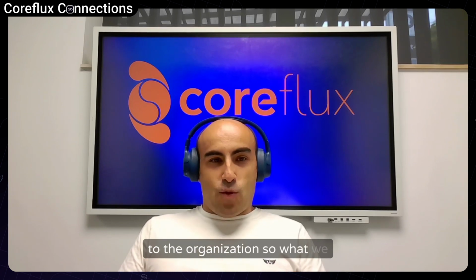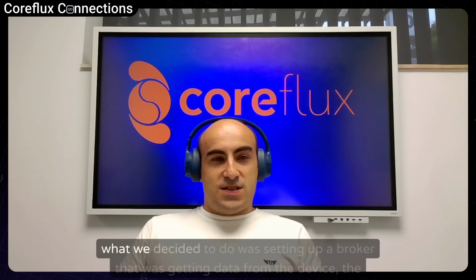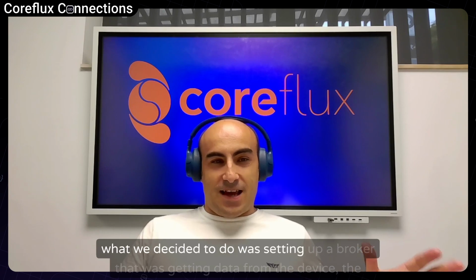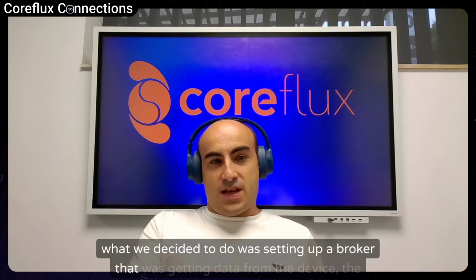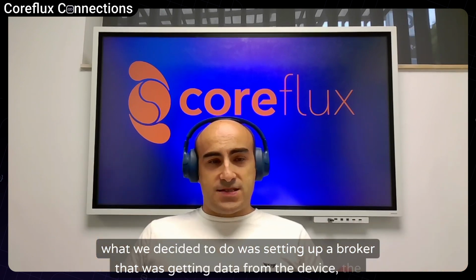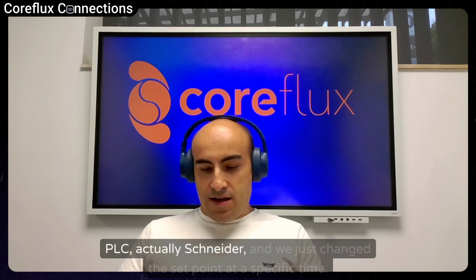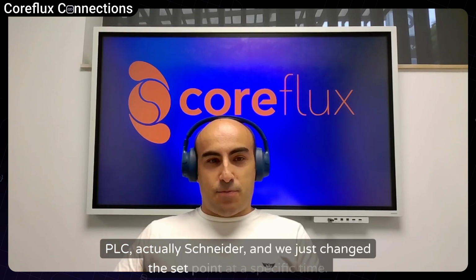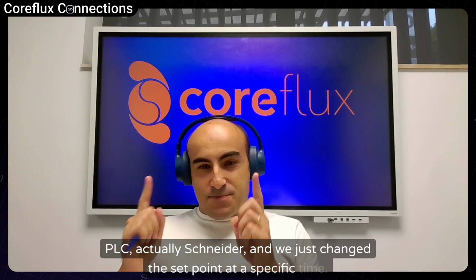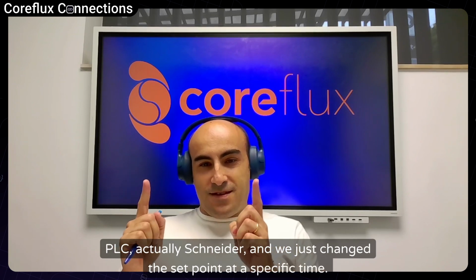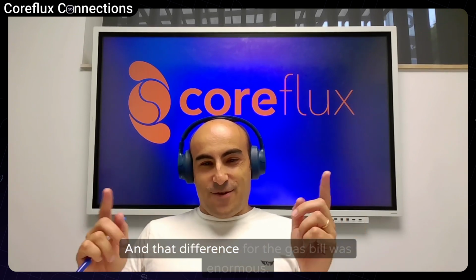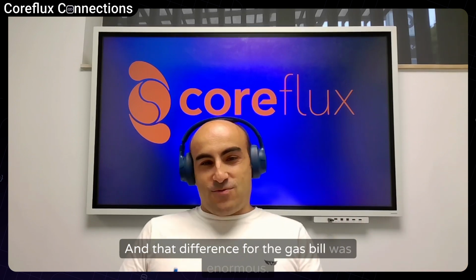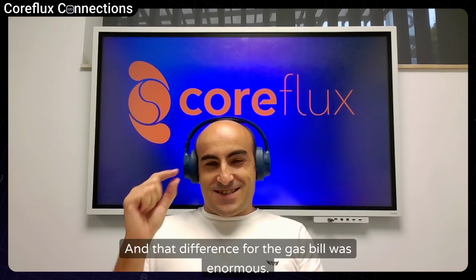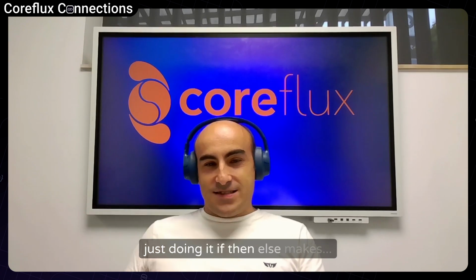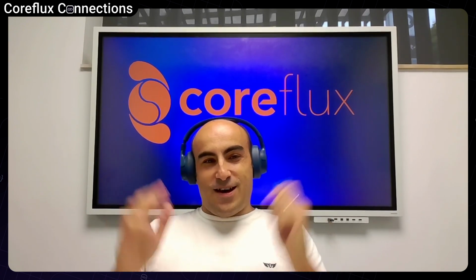So what we decided to do was setting up a broker that was getting data from the device, the PLC, actually a Schneider, and we just changed the set point at a specific time. And that difference for the gas bill was enormous. So just doing an if-then-else makes a change.